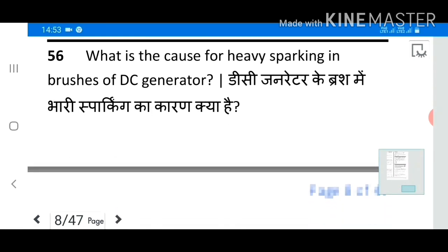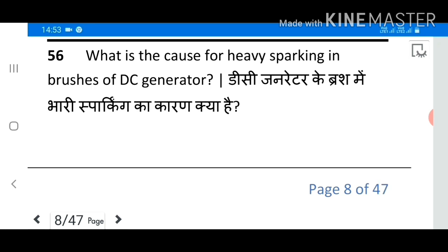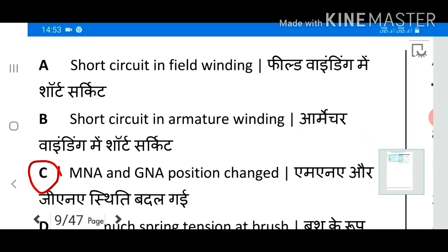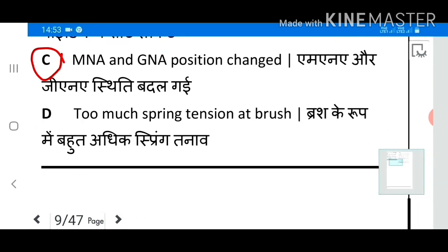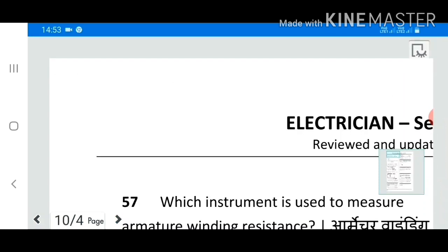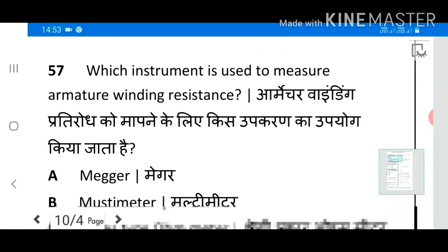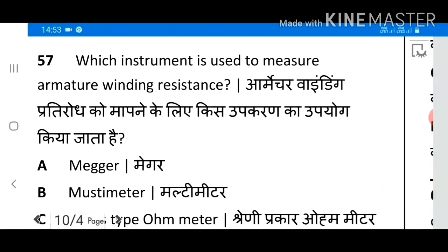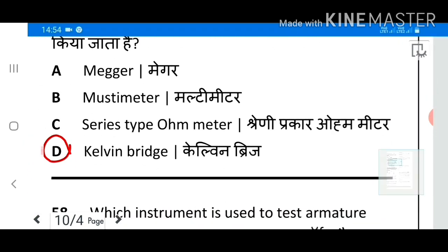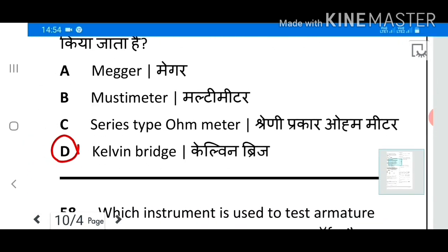Question 56: What is the cause for heavy sparking in the brushes of a DC generator? Answer: MNA and GNA position changed. Question 57: Which instrument is used to measure armature winding resistance? Answer D: Kelvin Bridge.